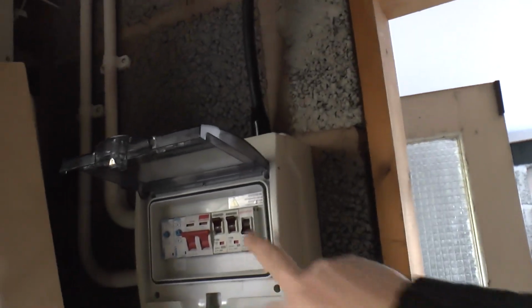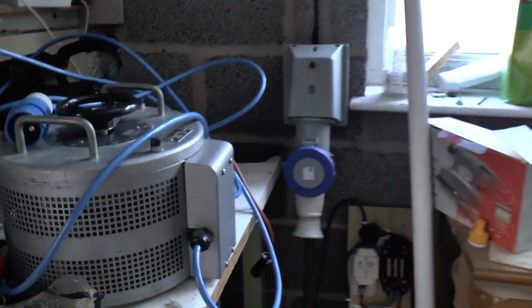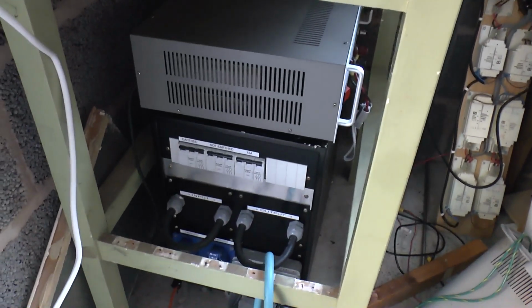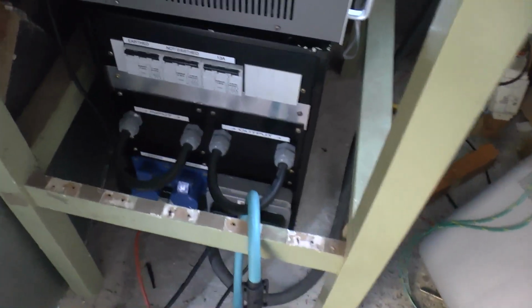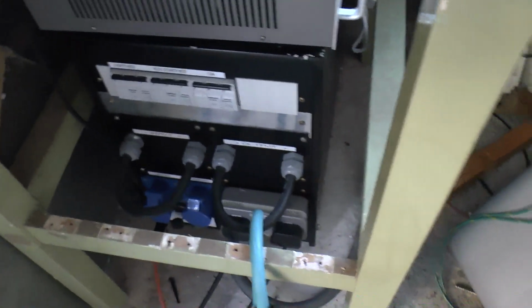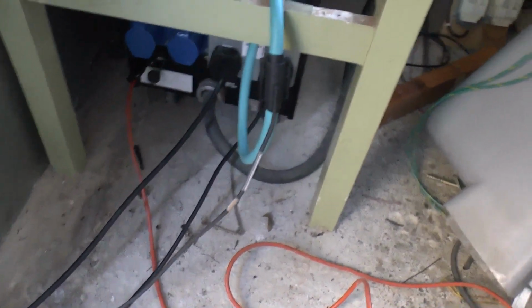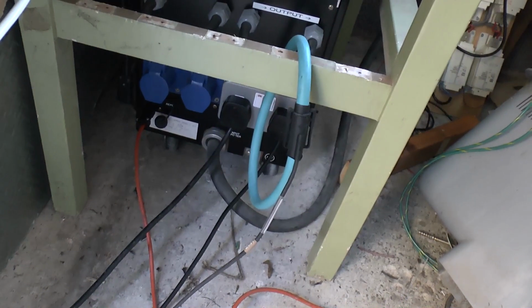So let's trace what we've got here. This is the breaker, which feeds that 63 amp socket, which feeds that mains conditioner. The output from the mains conditioner comes through that loop, so I can measure the current, and out through these sockets at the bottom.